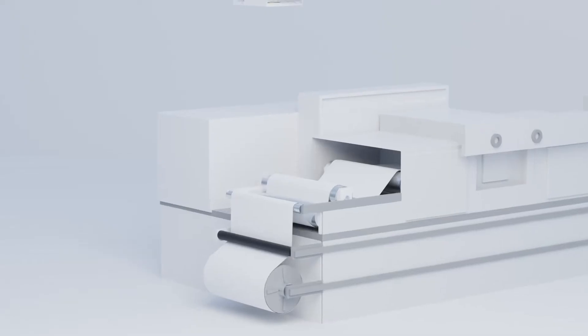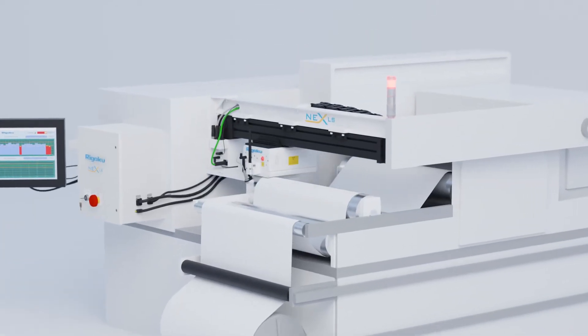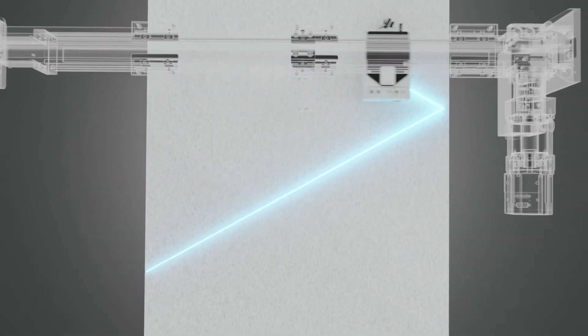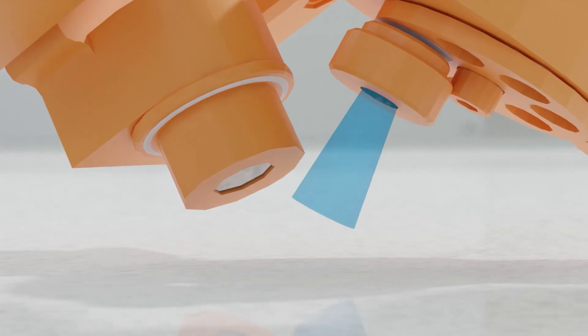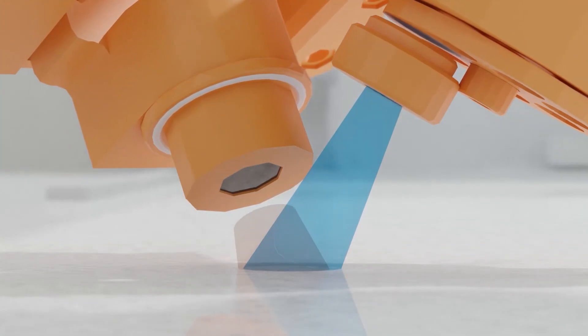NexLS is compact and allows users to self-install and customize the system to meet their process needs. Its analytical head sweeps back and forth across a moving web or coil. Source x-rays enter the product, exciting atoms in the material, and the elements in the coating excite and fluoresce characteristic x-rays back to the detector.